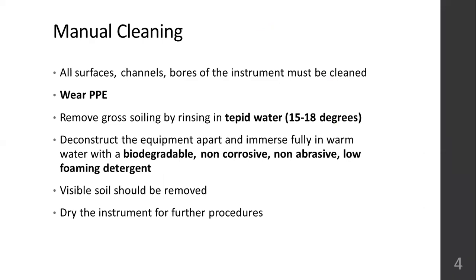Manual cleaning: all surfaces, channels, and bores of the instrument must be cleaned. You have to wear personal protective equipment while doing manual cleaning, and through this all the gross soiling is removed. The water should be tepid, a little bit lukewarm, around 15 to 18 degrees Celsius.